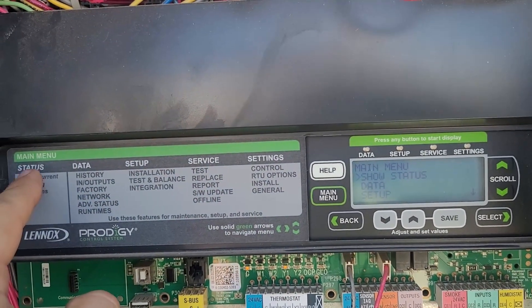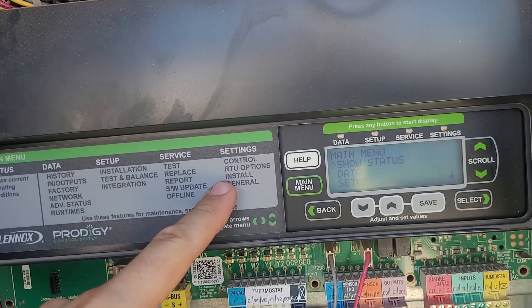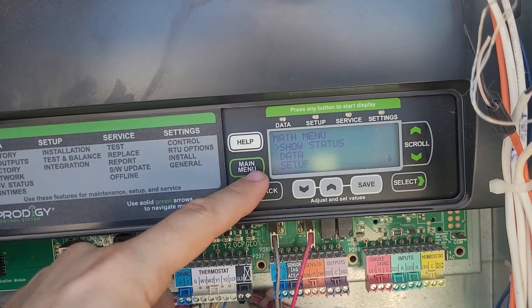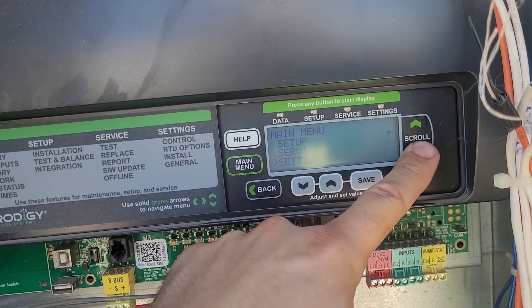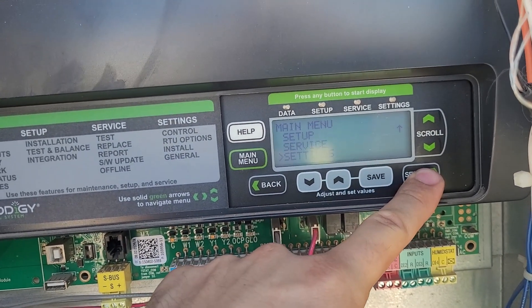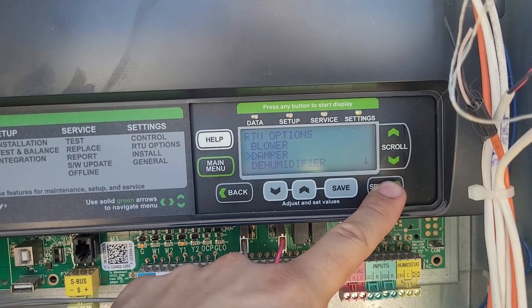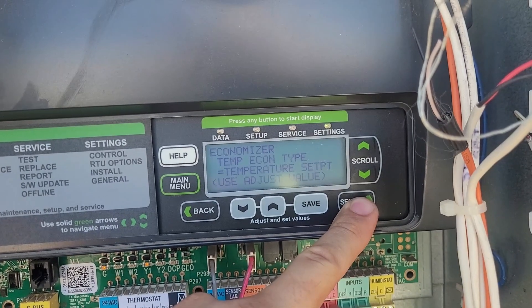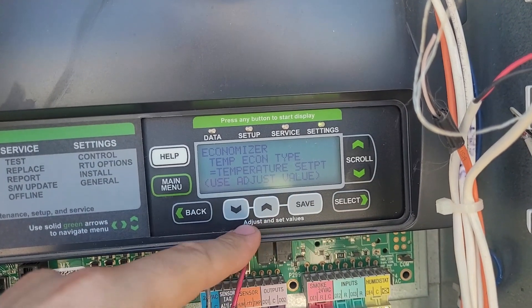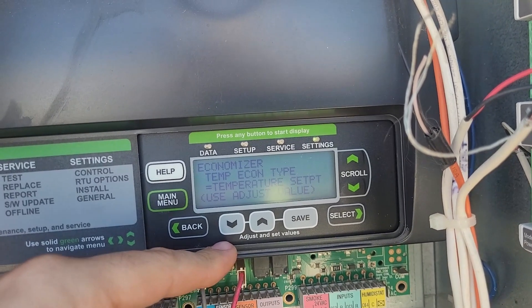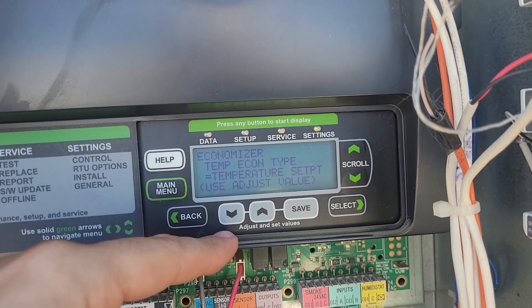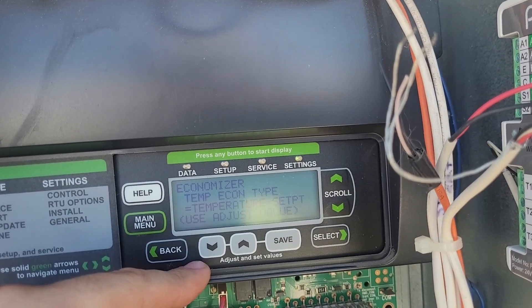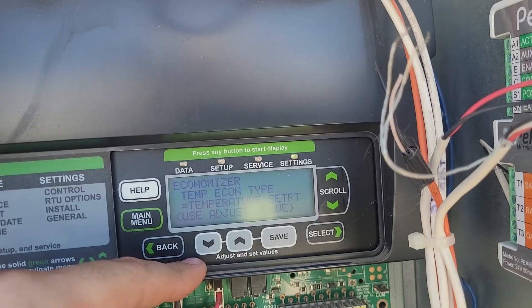In the main menu you have these categories. Go to Settings and check RTU Options. From the main menu, go down to Settings, then RTU Options, then Damper. The economizer is using temperature — sensible temperature — and that's what we want. If this said enthalpy or something else like global, we would need to change that, and I'll show you how to do that in just a minute.